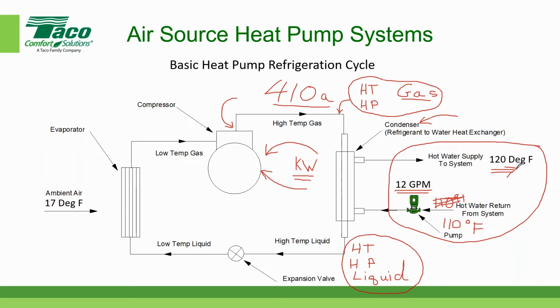Now, I've used 120 degrees Fahrenheit in my example here, where we return water temperature of 110. But most modern air to water heat pumps usually generate water temperatures as high as 140 degrees Fahrenheit using this conventional variable speed compressor and 410A. Now, there are air to water heat pump manufacturers that are experimenting with other refrigerants to get higher temperatures. But we're talking about the most common type of air to water heat pump. So they can generate water temperatures from 120 degrees to as high as 140 degrees pretty reliably. And now you can send that 140 degree water out into your system to heat your building.